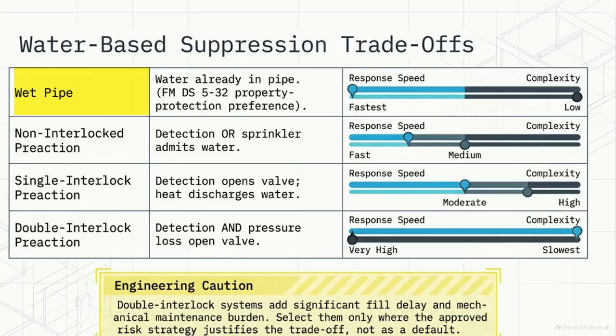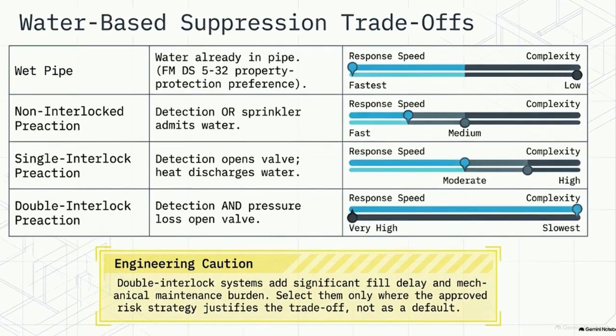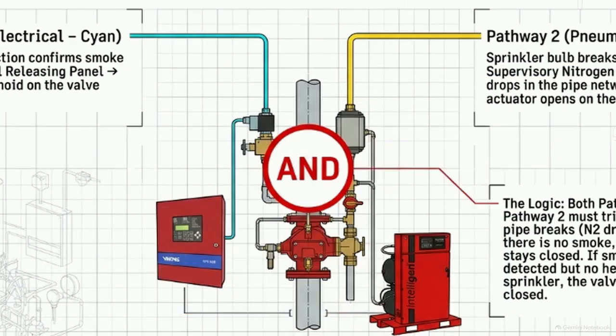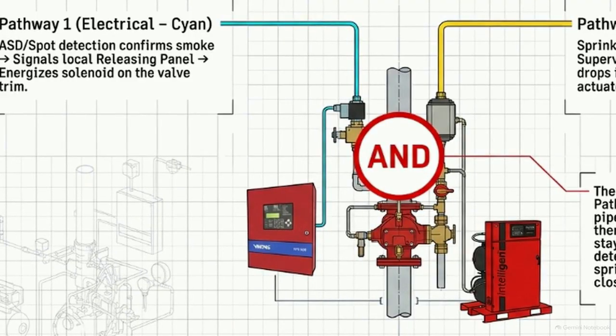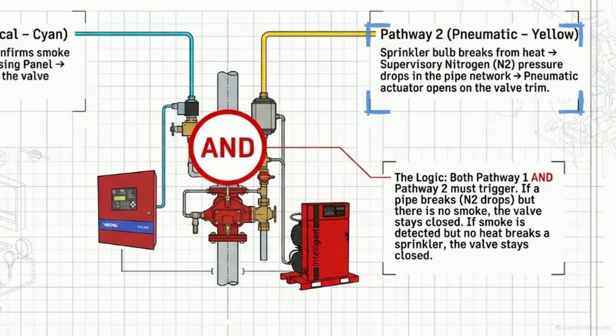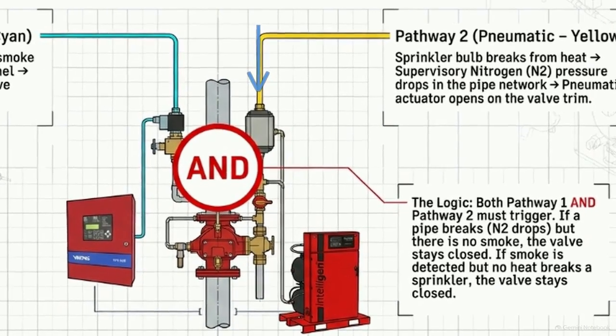This chart compares response speed and complexity between wet pipe and double interlock pre-action systems. Engineers select double interlock systems to prevent accidental water discharge over energized racks, despite slow fill delays and high maintenance burden. Opening the main suppression valve requires a specific sequence of logic centered around a mechanical AND gate. In Pathway 1, the ASD unit confirms smoke, signaling the control panel to energize the solenoid on the valve trim. Simultaneously, in Pathway 2, heat from the fire must break a sprinkler bulb. This causes supervisory nitrogen pressure to drop, opening a pneumatic actuator.